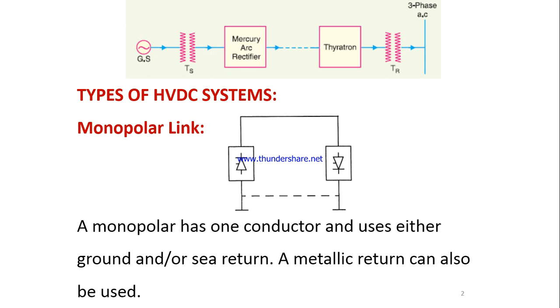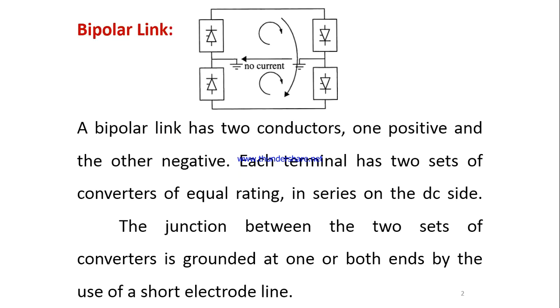Different types of HVDC systems are there. This is a monopolar link. A monopolar link has one conductor and uses either ground or sea for return. The metallic return can also be used here. Next is the bipolar link. The bipolar link has two conductors, one positive and the other negative, and each terminal has two sets of converters of equal rating in series on the DC side. The junction between the two sets of converters is grounded at one end or both ends by the use of short electrode lines. We can see this from the diagram itself.